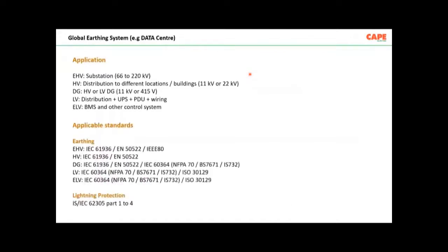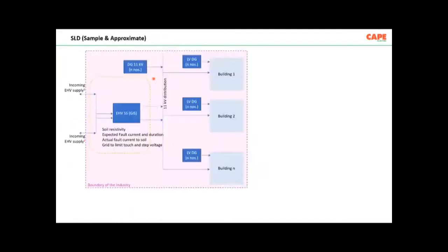Now, what do we do for modern buildings? For modern buildings, the recommended way of earthing is called global earthing. Global earthing is a typical earthing system which is achieved by interconnecting the earthing of extra high voltage, low voltage, your DGs, your UPS, ELV, and all these things together in a typical fashion so that the voltages are very much lesser. These are very well documented in the standards of IEC and EN standards. Of course, the IS standards are also upcoming.